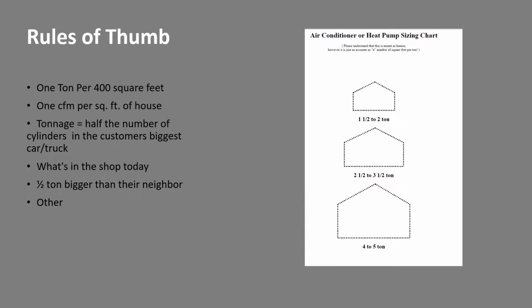1 ton per 400 square feet has been around for a long time. If that was ever correct, it was probably for a largely uninsulated house with single pane windows. So if it was ever correct, it's probably not correct today in modern homes with insulation and a higher degree of air tightness. The 1 CFM per square foot of house, I know that's out there. Tonnage, this is my favorite: half the number of cylinders in the customer's biggest car or truck, what's in the shop today, and of course, keeping up with the Joneses, half-ton bigger than the neighbors. And of course, we have other ones such as this nice little cutout over here where you stand across the street on the curb and see how big the house takes up.